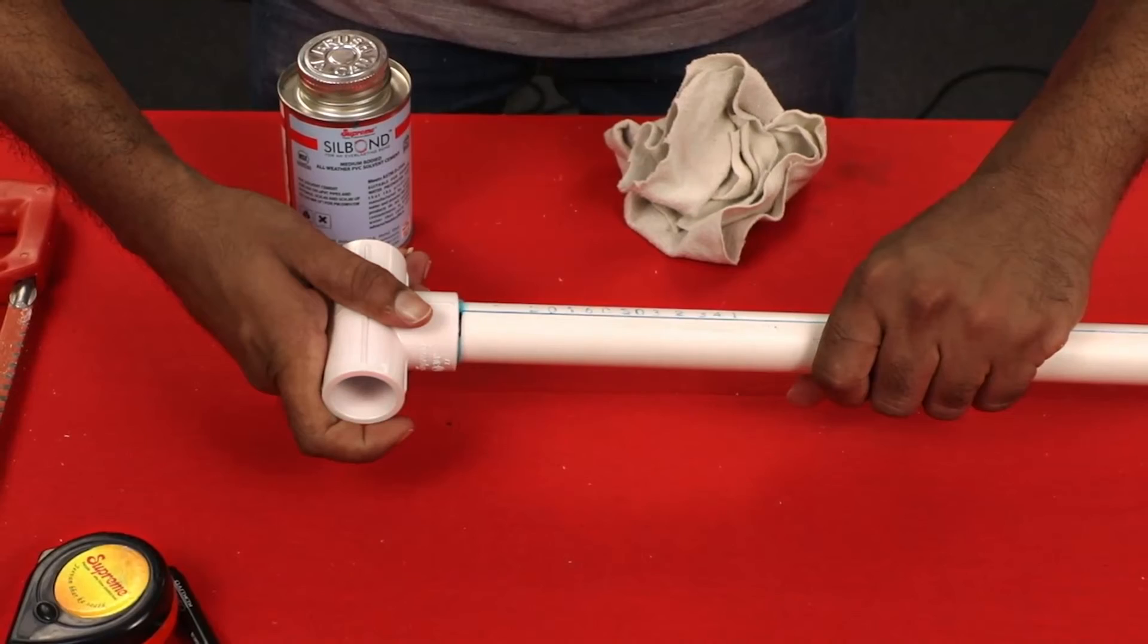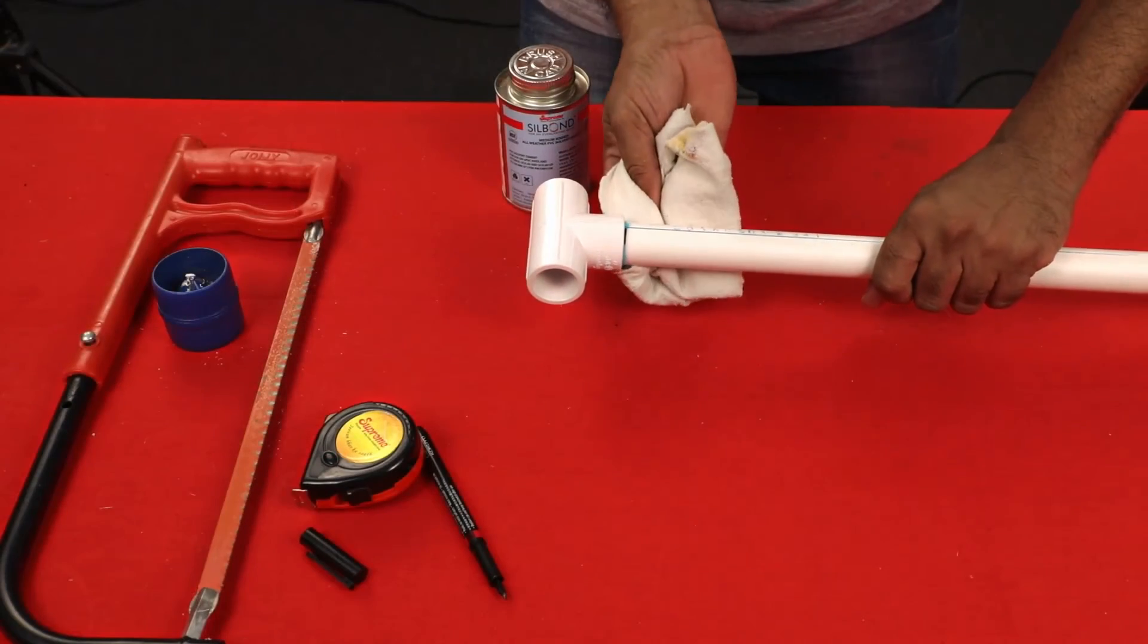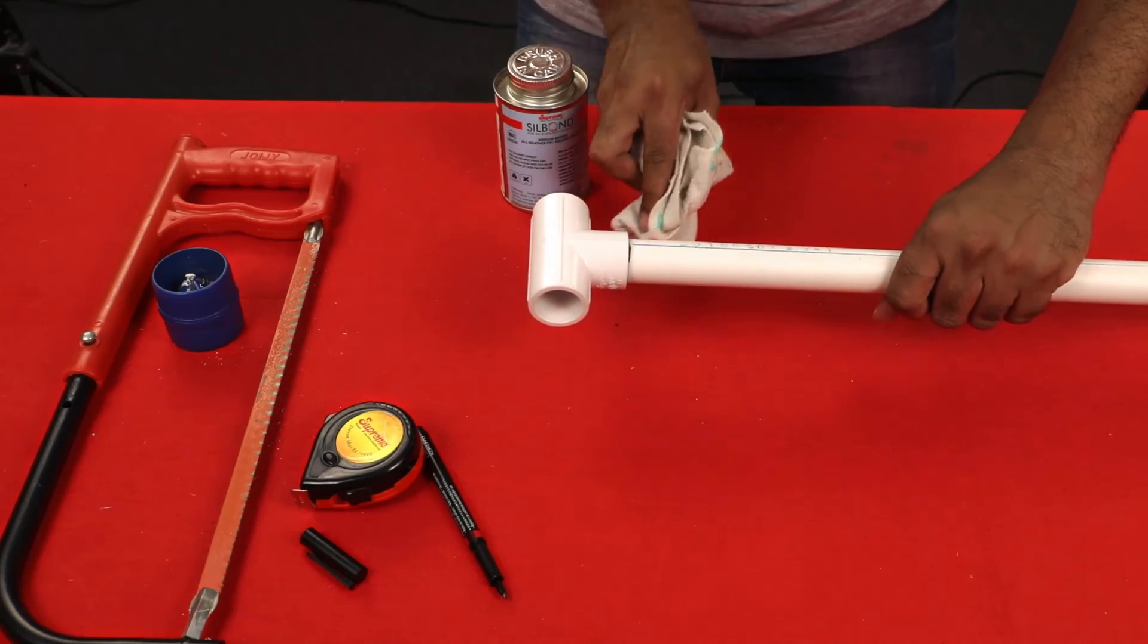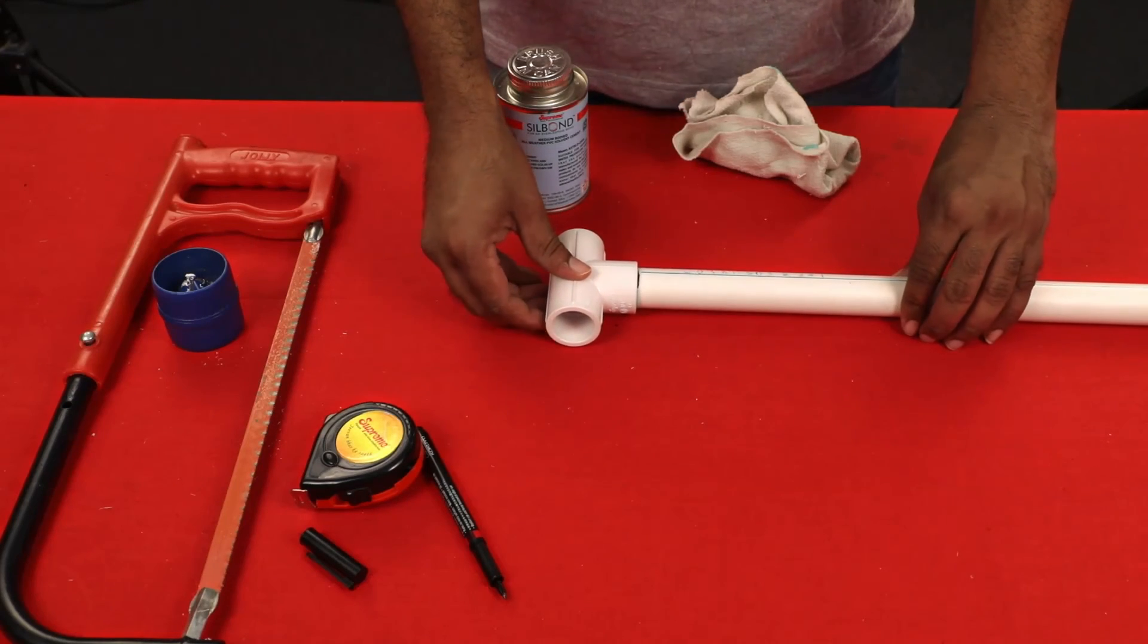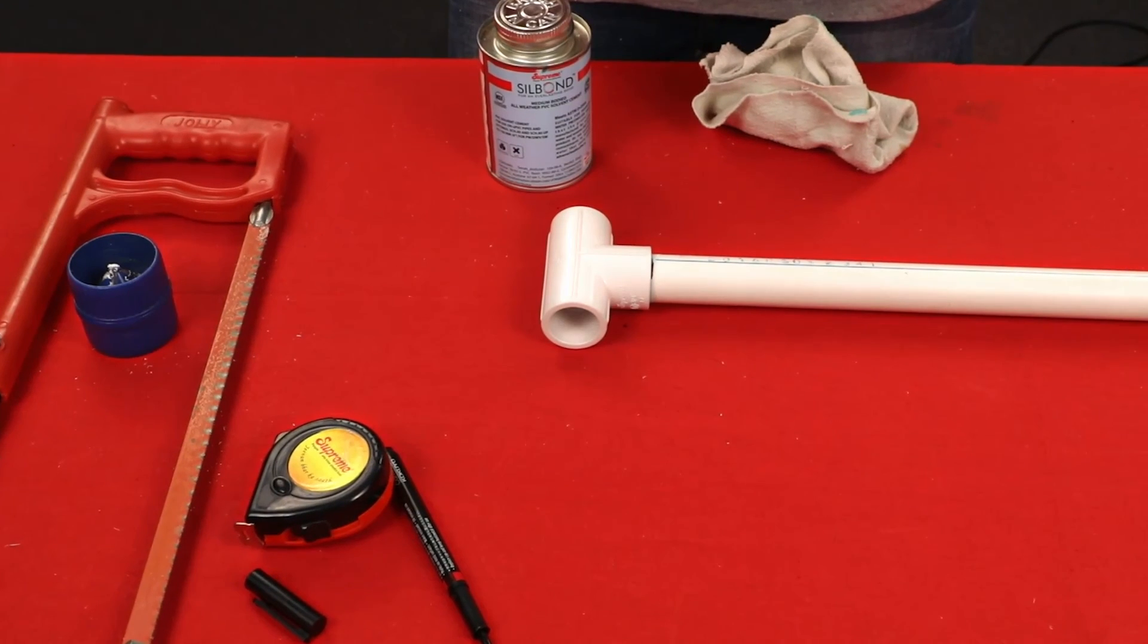Do not turn or twist the pipe or fitting once it is bottomed. Remove the excess cement from the pipe at the end of the fitting socket. The joint should not be disturbed or pressurized immediately after cementing to ensure proper curing, which normally takes about 12 hours.